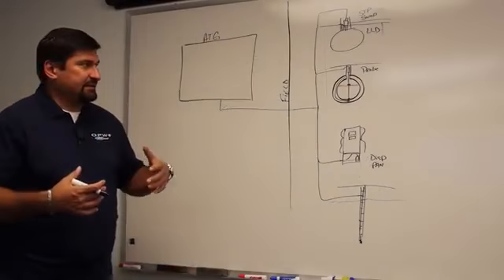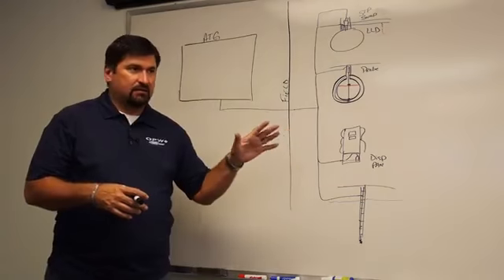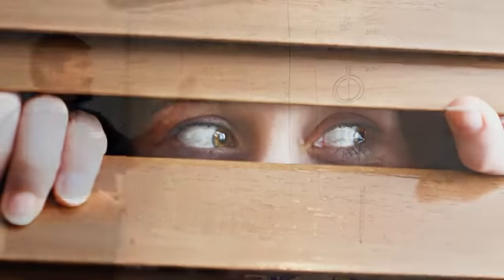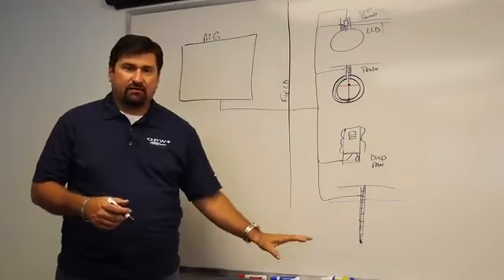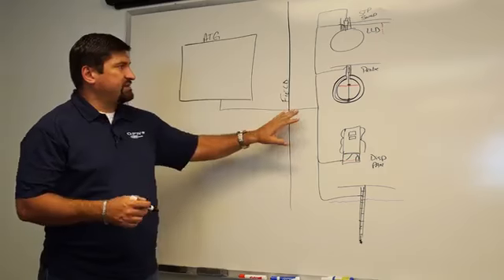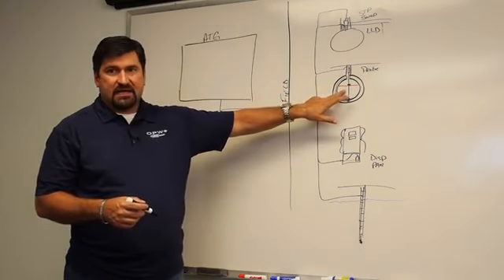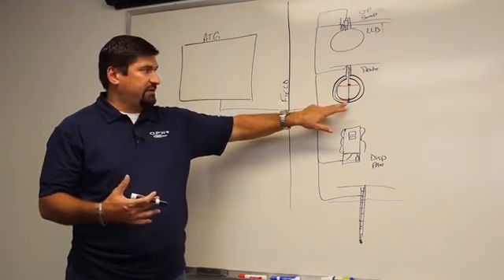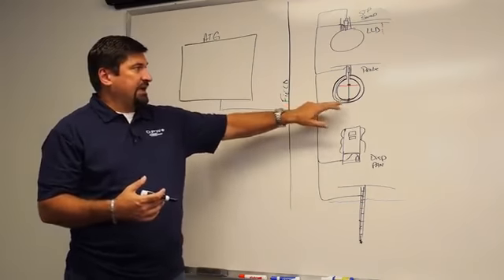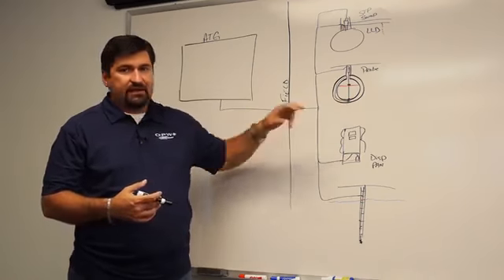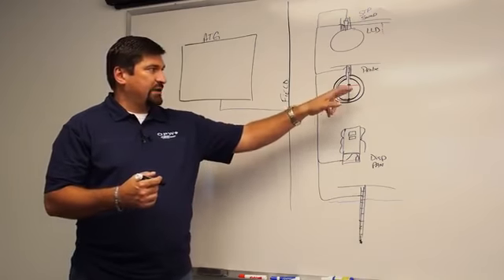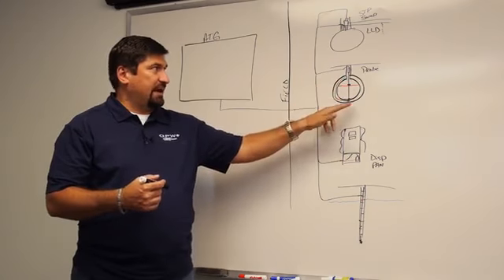So when we start looking at the tank gauge in a little bit different light, think of your ATG as that nosy neighbor or the neighborhood watch. It's constantly watching everything out in the field. So everything that's going on, it's monitoring the probe inside the tank to understand what the fuel level is, what the water level is in the tank. It's constantly watching to make sure that the annular sensor is not going off, to let you know that there's a breach between the inner and the outer wall.